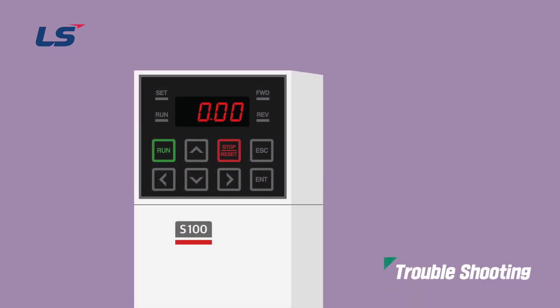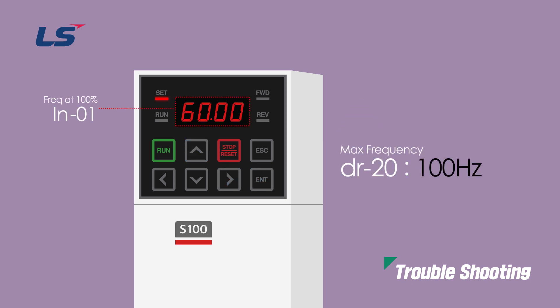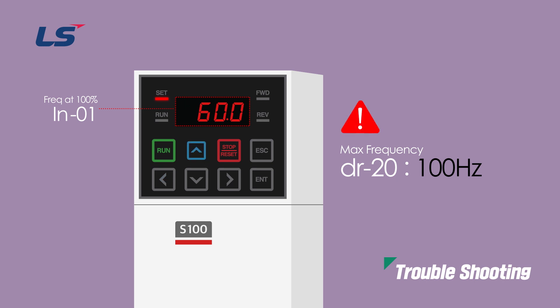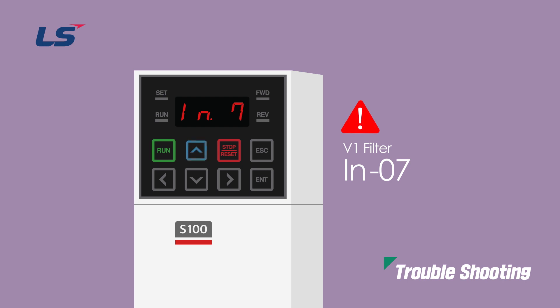The frequency at 100% input can be set in the IN01 parameter. Please be sure to check, as it is not always linked to the maximum frequency. If you set the maximum frequency to 100 Hz and want to drive at 100 Hz when the analog voltage reaches maximum, you must also change the value of the IN01 parameter accordingly. If the analog signal contains noise components, set IN group number 7, V1 filter high.